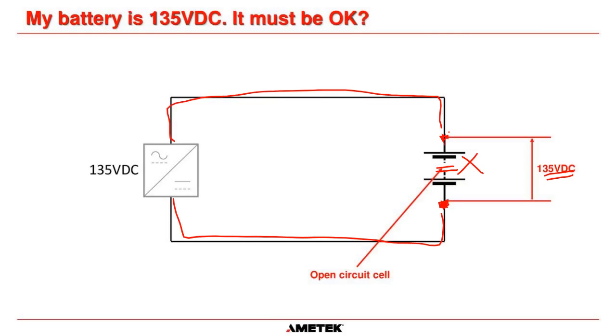So when people say, oh, I measured my battery, it's got 135 volts DC, so it must be good, that is not correct. You could have an open circuit in your battery. You're still going to measure 135 volts. That voltage doesn't tell you anything about the health of that battery whatsoever. So never, ever use the voltage of the battery with the charger connected as giving you the state of health of the battery. That is completely and utterly incorrect. All you are measuring is the charger voltage at this point here. Hopefully that explained that misconception.